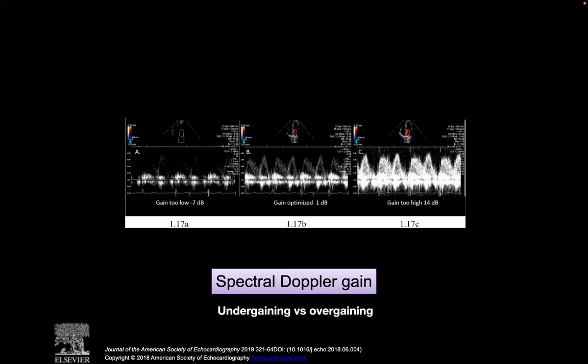Spectral Doppler gain, as we discussed during your overall gain settings, there's a knob or dial there for your spectral display gain, and overgaining and undergaining can occur in that one. If you look at the images here, we're taking some images from the pulmonary vein. When your gain is set too high, it's very fuzzy, it's all very white, and you don't really know what's going on. When it's undergained, again you're losing a lot of information, you don't see what exactly is happening there. That's why an optimally set spectral Doppler gain is fairly important, with a good spectral window, modal velocity, and all of the above that we discussed previously.